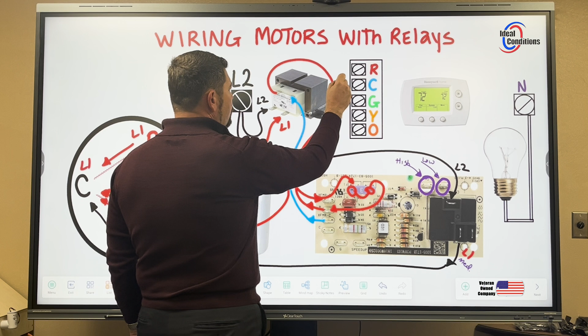Now, with the 24 volts here through the board, I have 24 volts on this left-hand part of my fuse. As long as the fuse is closed, as long as we don't have an open fuse here, then I'll have 24 volts here, and out of this, 24 volts will be present right here on R. So basically, as long as our fuse is good, we'll have 24 volts as an output on R. The first one is an input, the second one is an output, and that's what we're going to run up to our terminal block here.